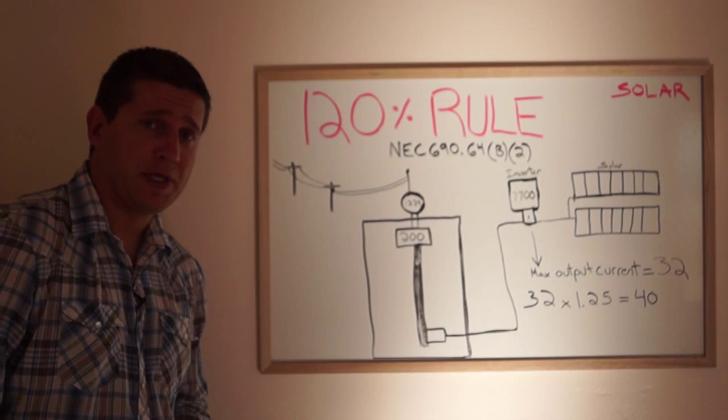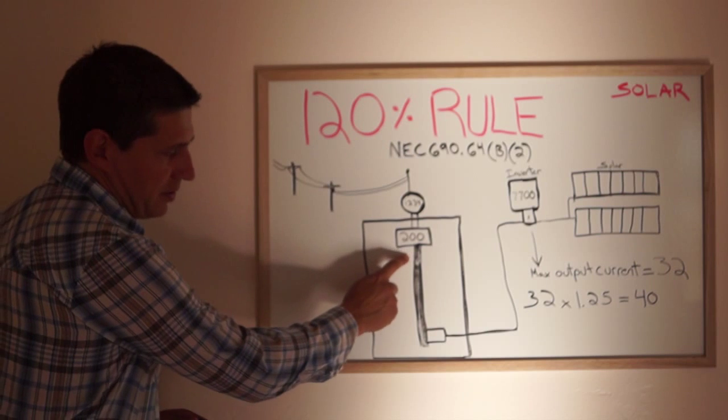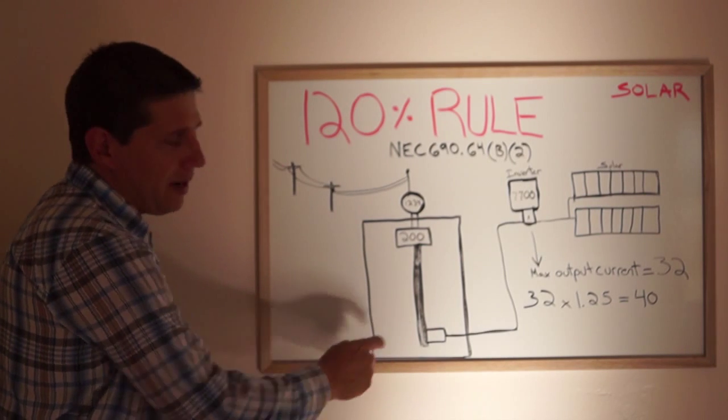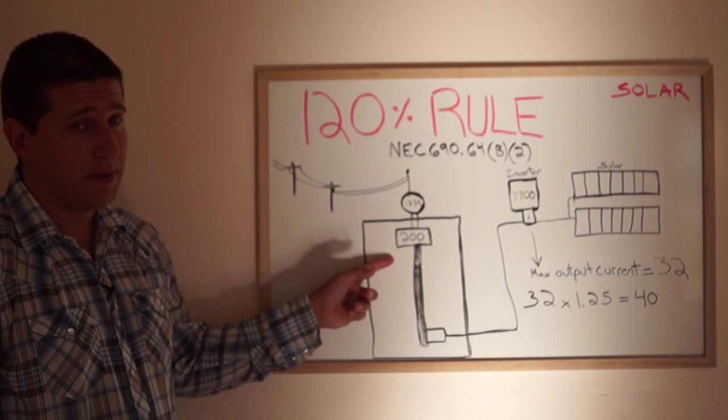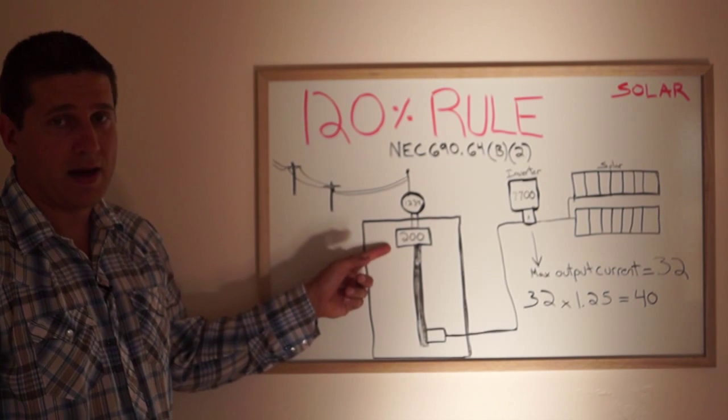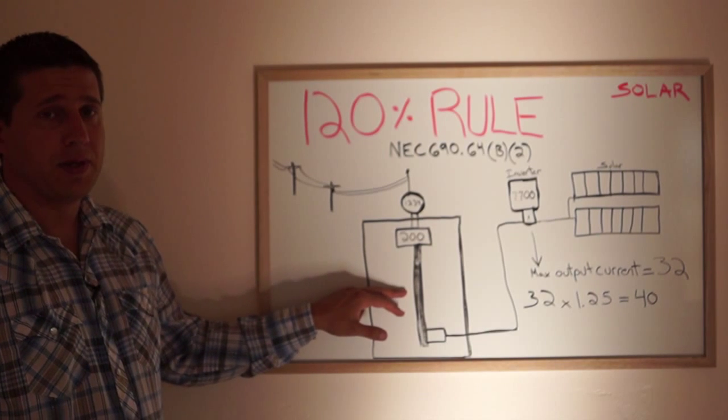And what the 120% rule states is that after this breaker there's a bus bar, and that bus bar has a rating. Generally if the breaker has a 200 amp main breaker located on it, on the panel, generally that bus bar is 200 amps as well.